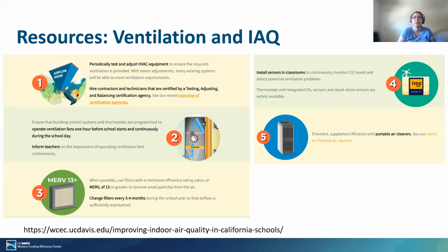But anyways, step 1, you want to test HVAC equipment to ensure that it's delivering the design ventilation rate. And there's a process to do that I'm going to talk about. 2, you have to be operating your fans on your HVAC systems to provide that outdoor air. That seems obvious, but can be a problem.